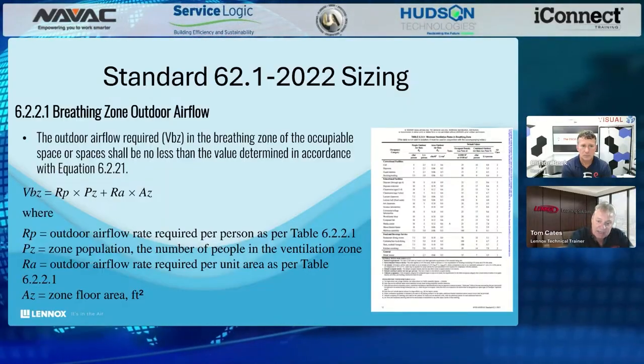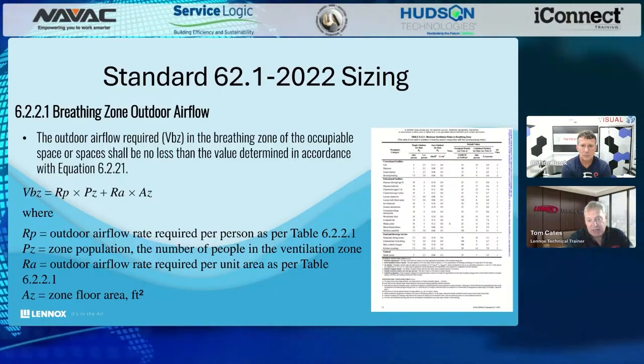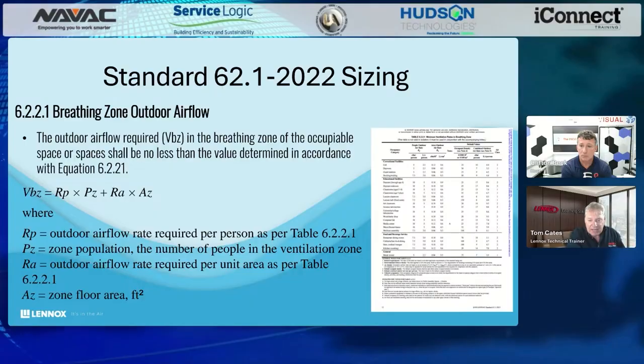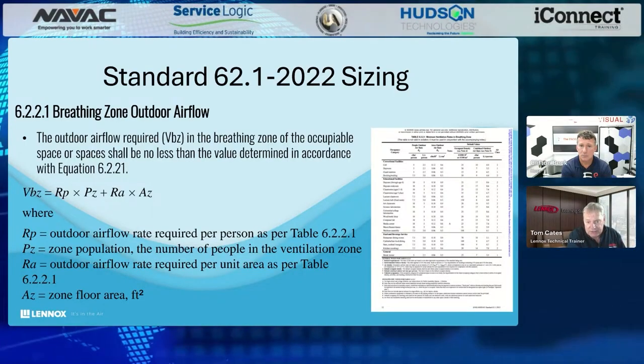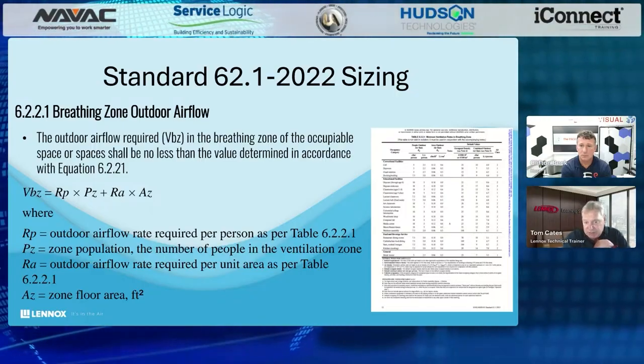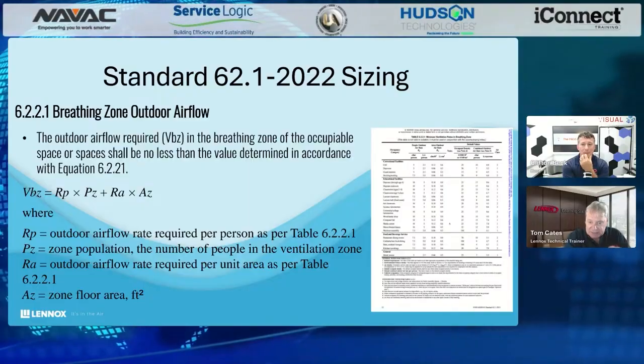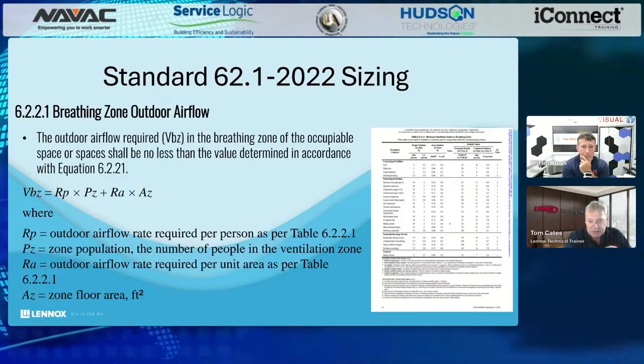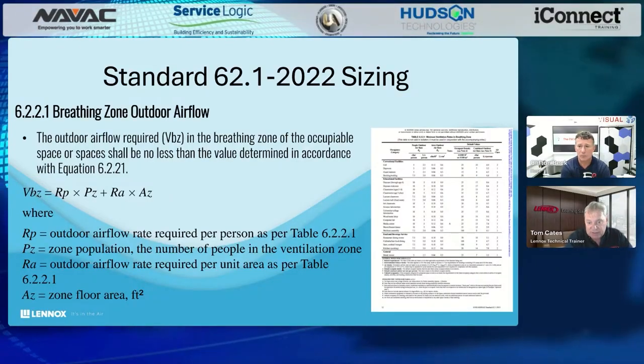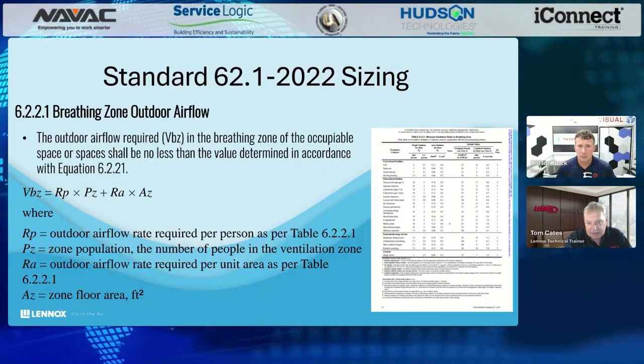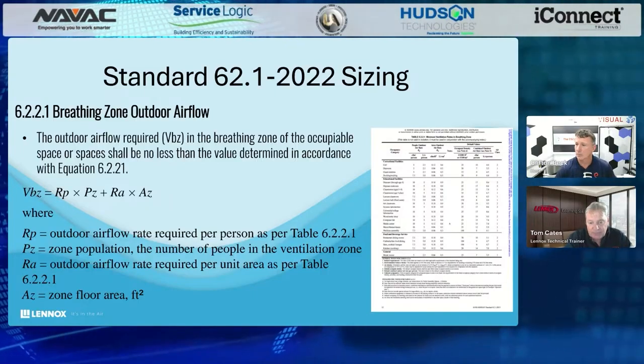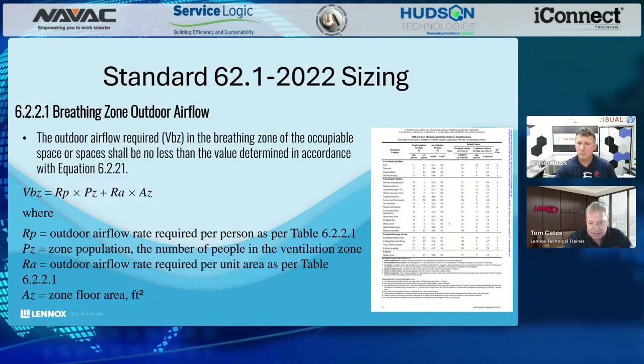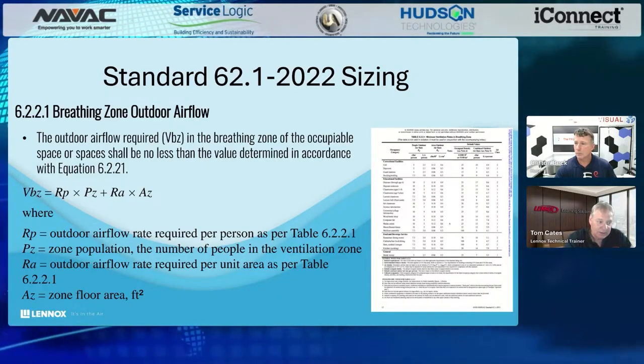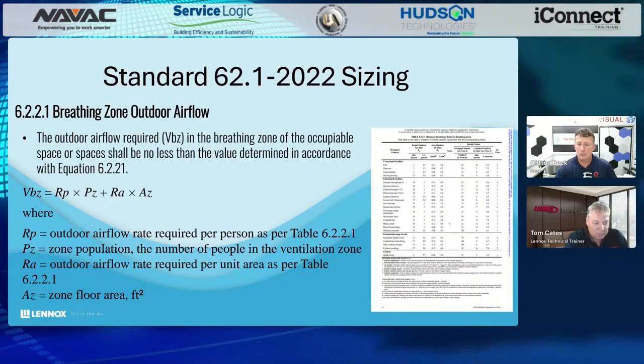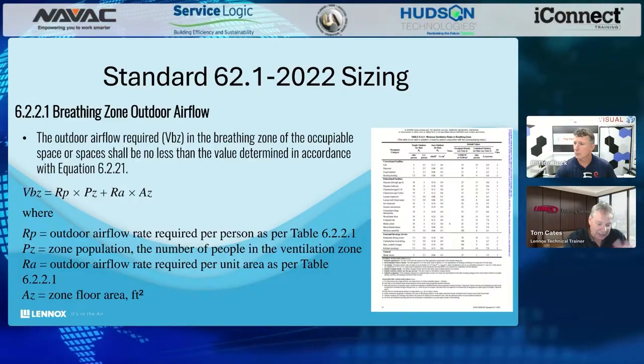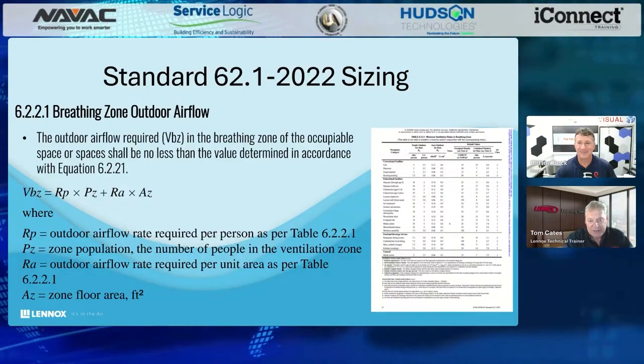And then it's going to assign a ventilation rate per person that is going to be using that space. So somebody in an office, say, is probably going to require a lower ventilation rate per person than somebody who's in a gymnasium who's working out, who's using a lot of oxygen, right? So it sets the types of buildings that the ventilation has to be provided to, the rate at which the occupants are essentially going to consume that fresh air, and then it looks at the size of the building, and again, how that building is being used. So it takes those four pieces of information, and with that we can calculate what the ventilation rate is. And the formulas here come with acronyms that go along with them. I'm not going to get into all the details in the hour we've got here, but that is a brief explanation of how they do it commercially.